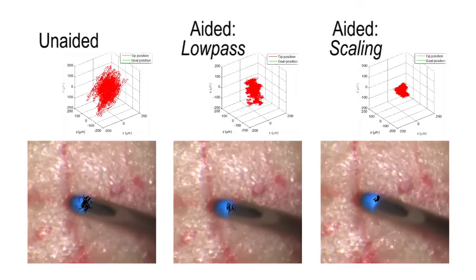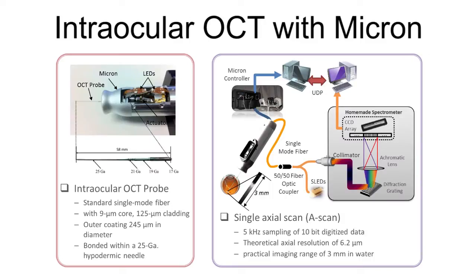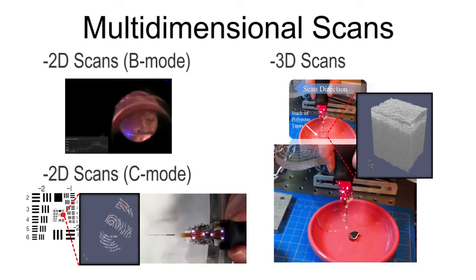Micron can be seen to reduce hand tremor significantly during vitreoretinal microsurgery. Micron can also be utilized in handheld scanning for intraocular optical coherence tomography. For handheld OCT imaging, a single fiber OCT probe is integrated with the Micron system. It can detect retinal structures up to 3 mm below the surface with micron resolution. The capability of fine manipulation in Micron enables multidimensional scanning. B-mode scans are achieved by scanning the OCT probe laterally, and with spiral scans of the tooltip, en face reconstruction is also possible.